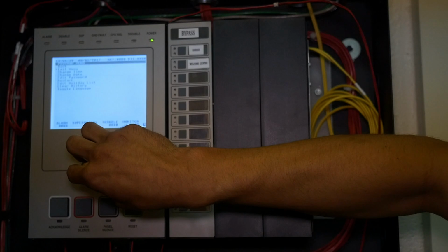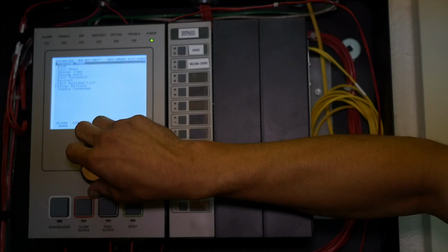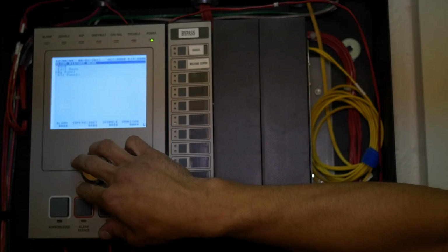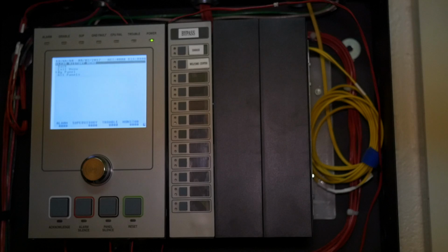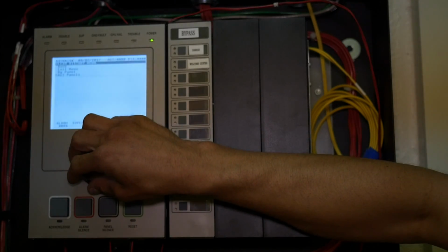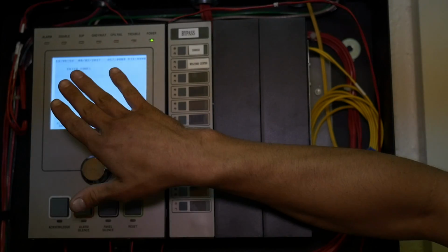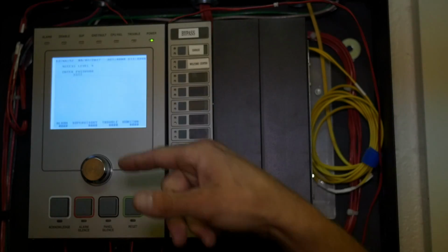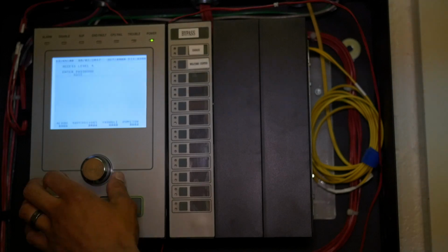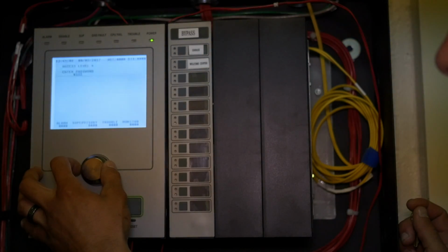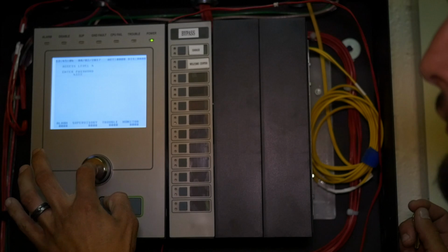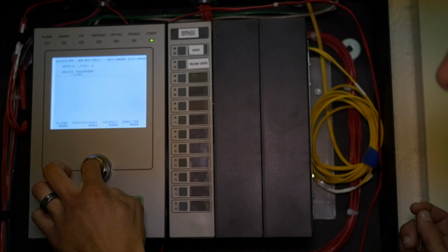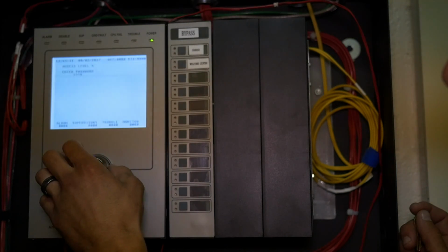Program, and there's an option, the second one from the bottom is clear history. Enter. You can either do it by all the panels on this network, which would be this panel and the panel up there, or you can do it by specific panel. So if we wanted to just clear the history on this panel, we would enter the panel number and enter, and then it's going to ask you for a level 4 password. That is just 4 4s, and you'll have to use the rotary dialer to turn over to 4, enter, 4, enter, 4, enter, and 4, enter.